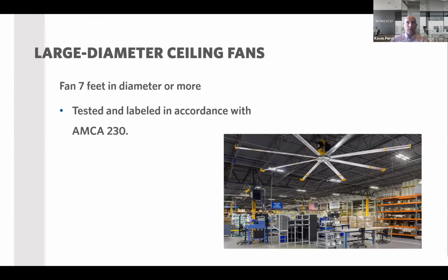And the last thing we'll talk about in the mechanical section here are large diameter ceiling fans. I'm sure we have all seen these big fans, but really any fan 7 feet in diameter or bigger, that's what it's saying, has to be tested and labeled according to the AMCA 230. Is that a big deal? Probably not, but just know they're now starting to require that.